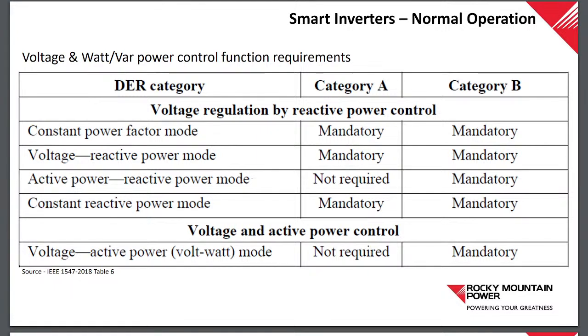What's happening is with the new IEEE 1547 2018 standard, they came out with a 1547.1, which is the testing standard. Then you'll hear people talk about UL 1741, which is the testing that certifies against the IEEE standard. There are different versions of the UL standard: 1741 SA, which incorporated the California and Hawaii rules, and now UL 1741 SB, which certifies against the new IEEE 1547 standard. So every inverter manufactured with that UL 1741 SB certification has the capability to do category A or category B - they have to be able to do one or the other, or both. We just have to select which one we want.